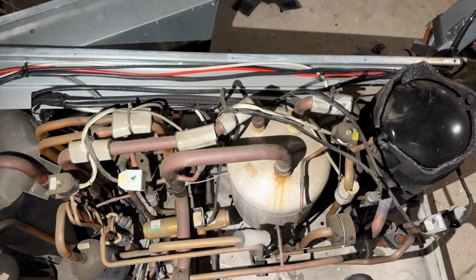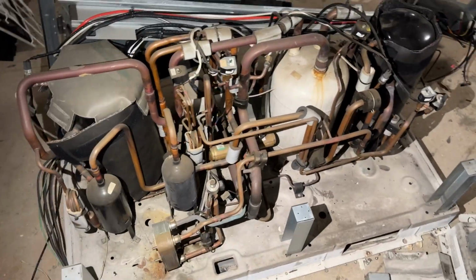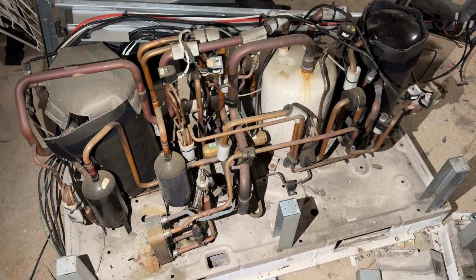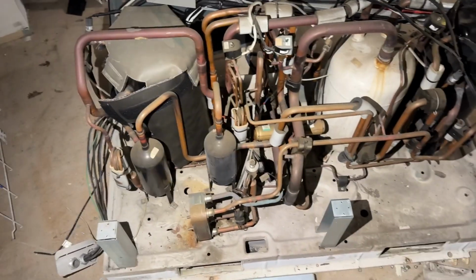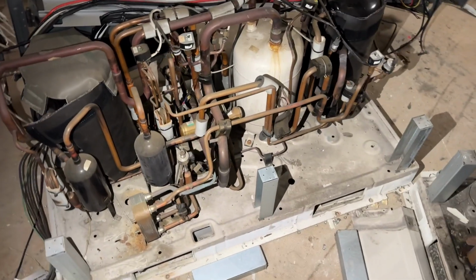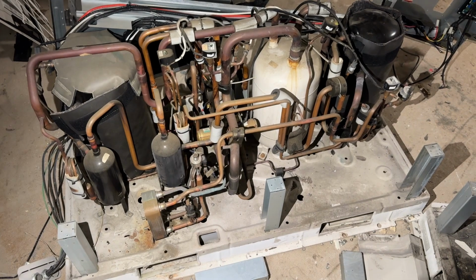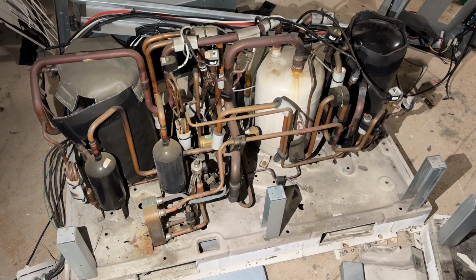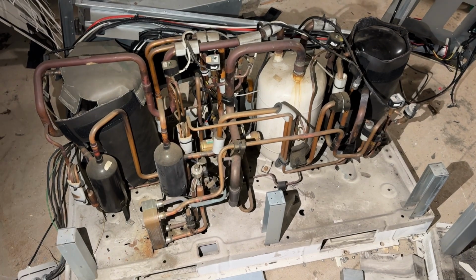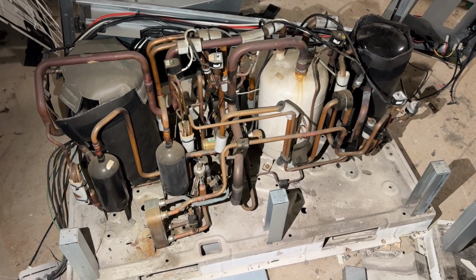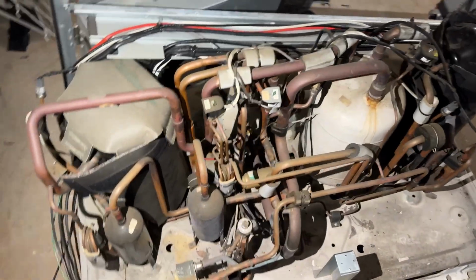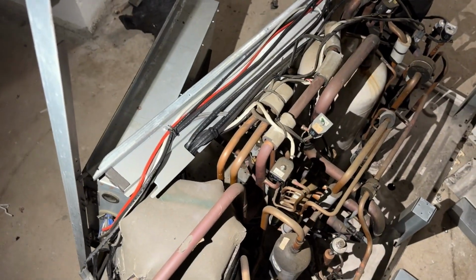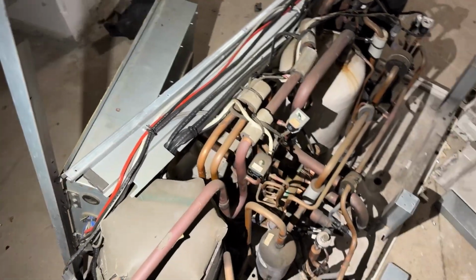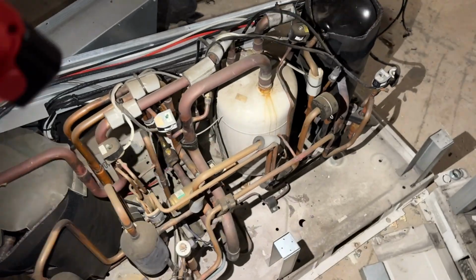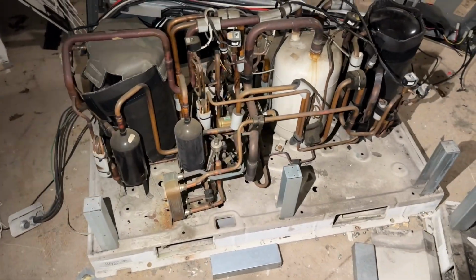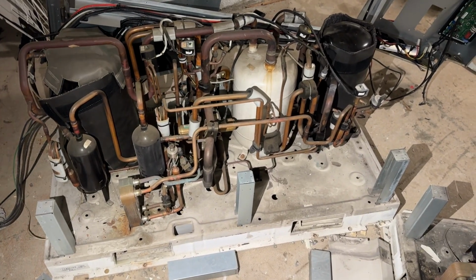But I think that pretty well covers it. Even though this is an old gen, this is really similar, except your city multis are a bit different in that this subcooler is in the branch box. That's how they get away with having just two pipes to the branch box, because the branch box is really doing a lot of liquid handling, and that's completely different from every other unit because Mitsubishi patented that. Every other unit is going to be sending out that liquid line, and the branch boxes aren't doing much other than distributing whichever the indoor unit wants, whether discharge, gas, or liquid.